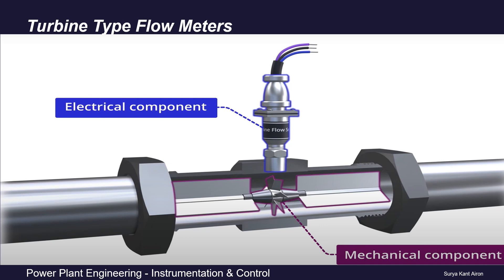A simplified scheme of such flow meters consists of three parts: mechanical components, which include the turbine — that is the rotor, impeller, and blades; electrical components, which are the pickup sensor with a transmitter; and the housing, which covers both mechanical and electrical components. The mechanical components include a turbine consisting of a shaft fixed to the pipeline and an impeller, which is a multi-bladed wheel attached to a shaft that rotates on bearings. The blades are made of ferromagnetic material.